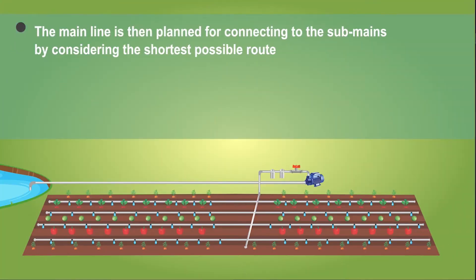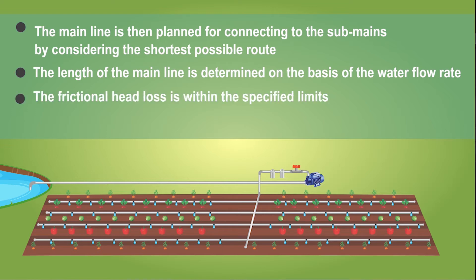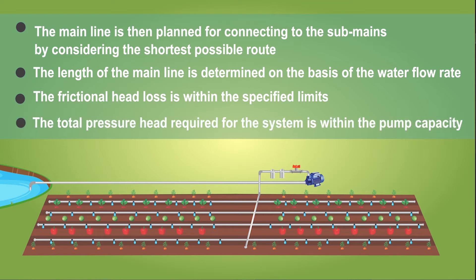The main line is then planned for connecting to the sub-mains by considering the shortest possible route. The length of the main line is determined on the basis of the water flow rate so that the frictional head loss is within the specified limits and the total pressure head required for the system is within the pump capacity.